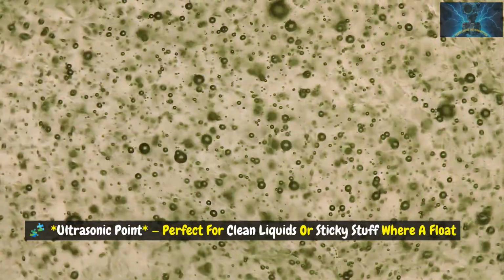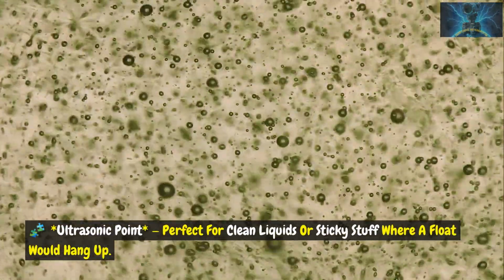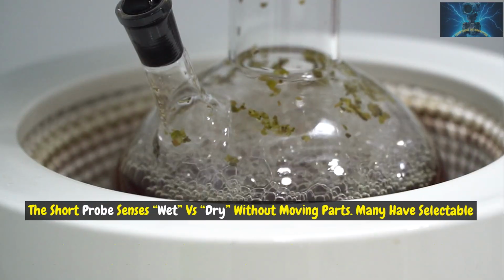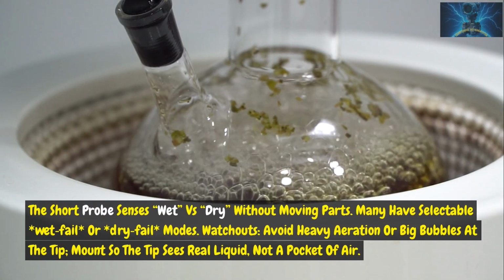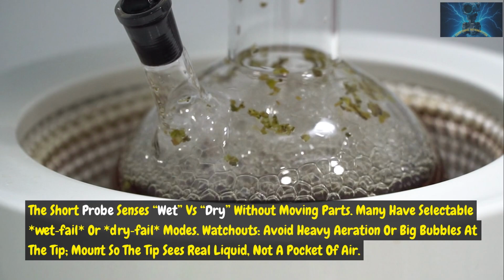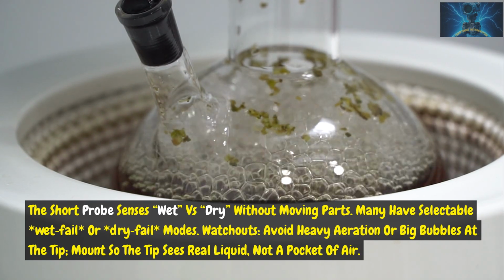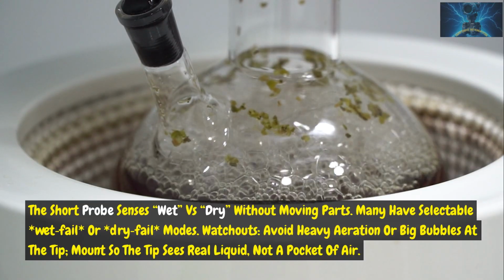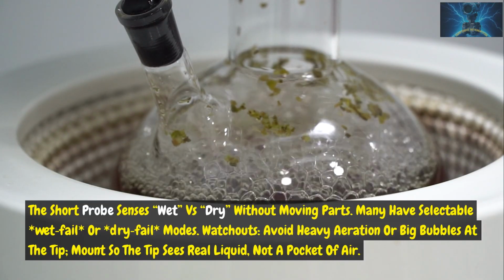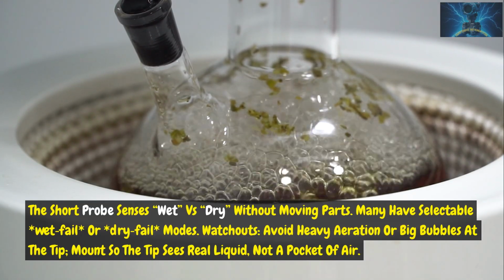Ultrasonic point: perfect for clean liquids or sticky stuff where a float would hang up. The short probe senses wet versus dry without moving parts. Many have selectable wet fail or dry fail modes. Watchouts: avoid heavy aeration or big bubbles at the tip. Mount so the tip sees real liquid, not a pocket of air.